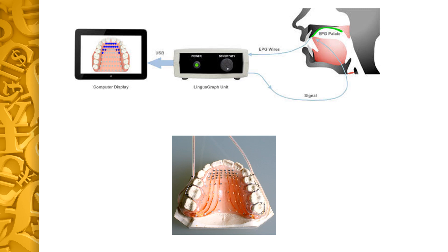Coming to electropalatography, it is a technique used to monitor the contacts between the tongue and the hard palate, particularly during articulation and speech. Here, a custom-made artificial palate is molded to fit against the speaker's hard palate, and this artificial palate contains electrodes exposed to the lingual surface. When contact occurs between the tongue surface and any of the electrodes, particularly between the lateral margins of the tongue and the borders of the hard palate, then electronic signals are sent to the external processing unit.